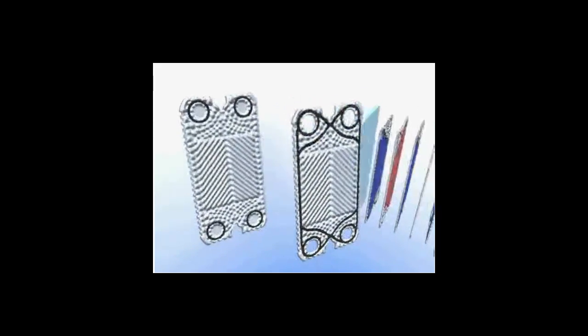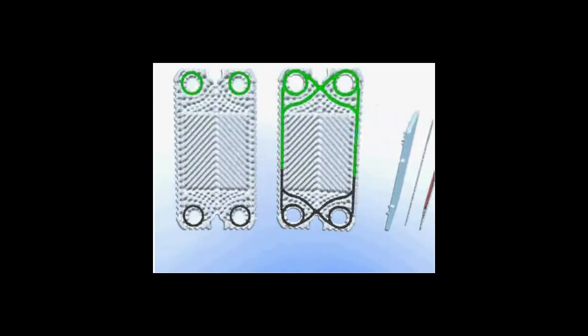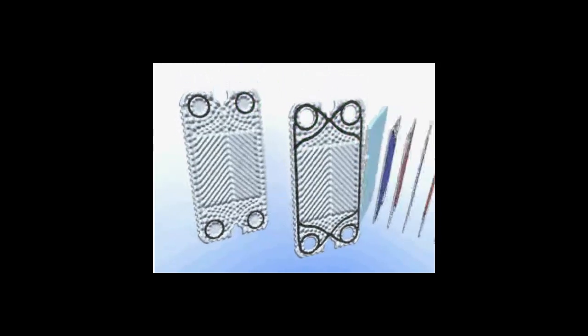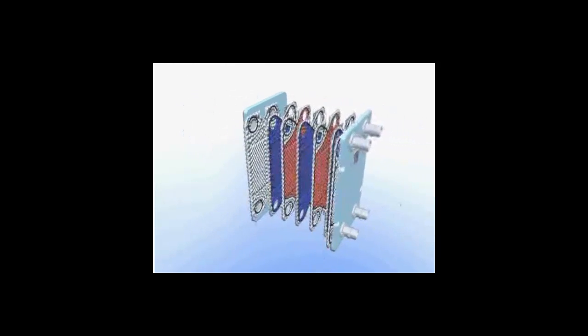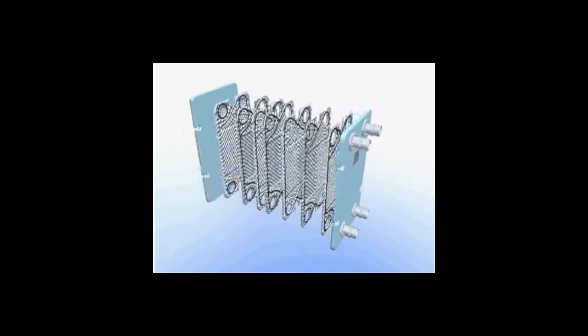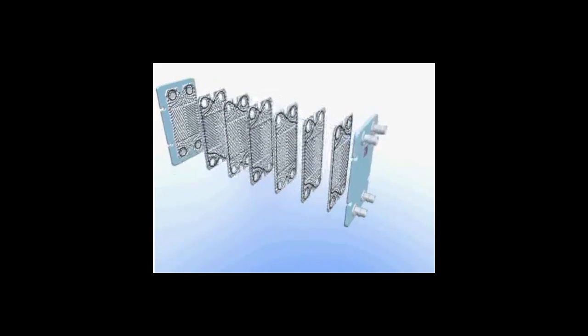Special plates called end or transition plates with unique gaskets and blocked ports direct overall product and utility flow in a pass. These plates are used at the end of a pass or next to the frame. Looking at flow in this one-pass configuration.